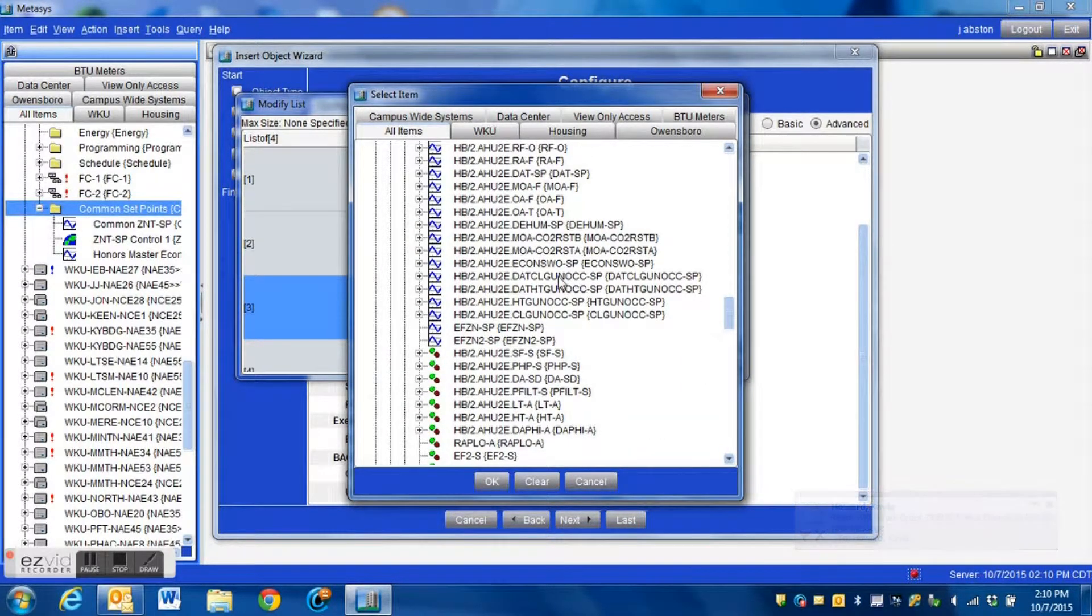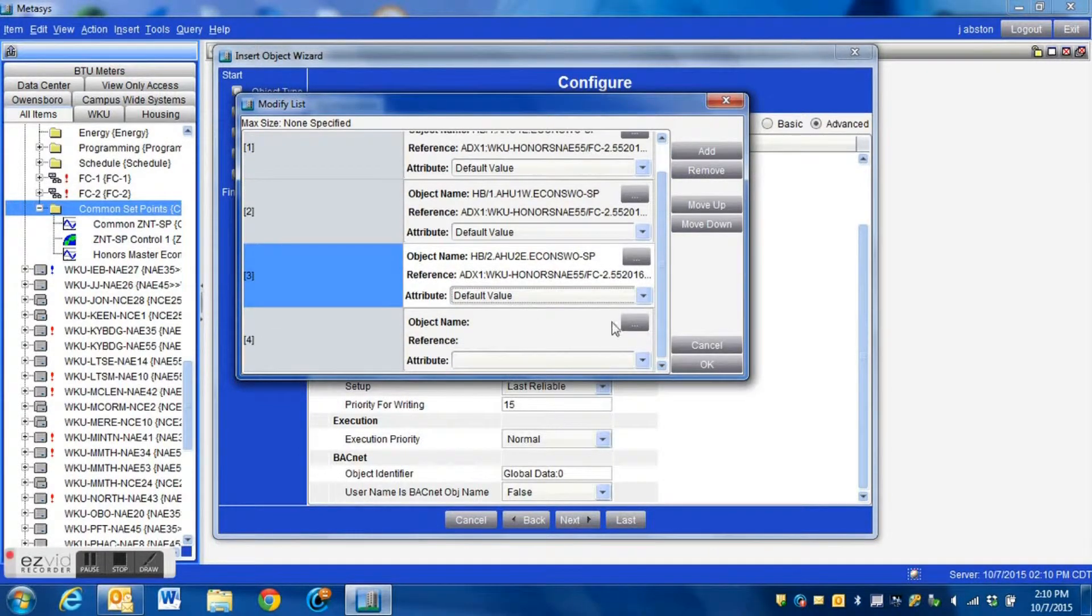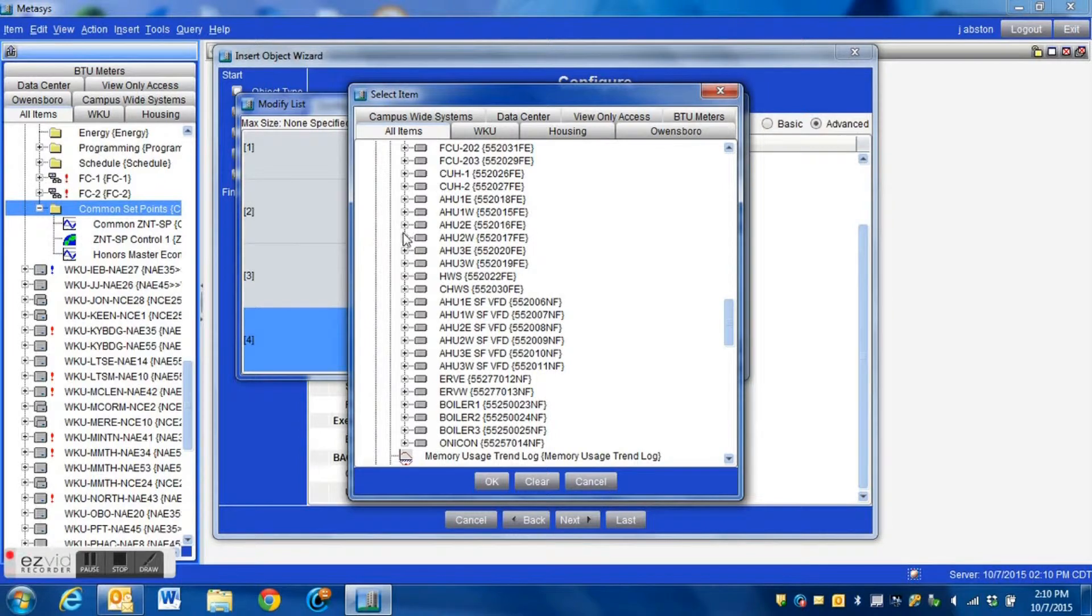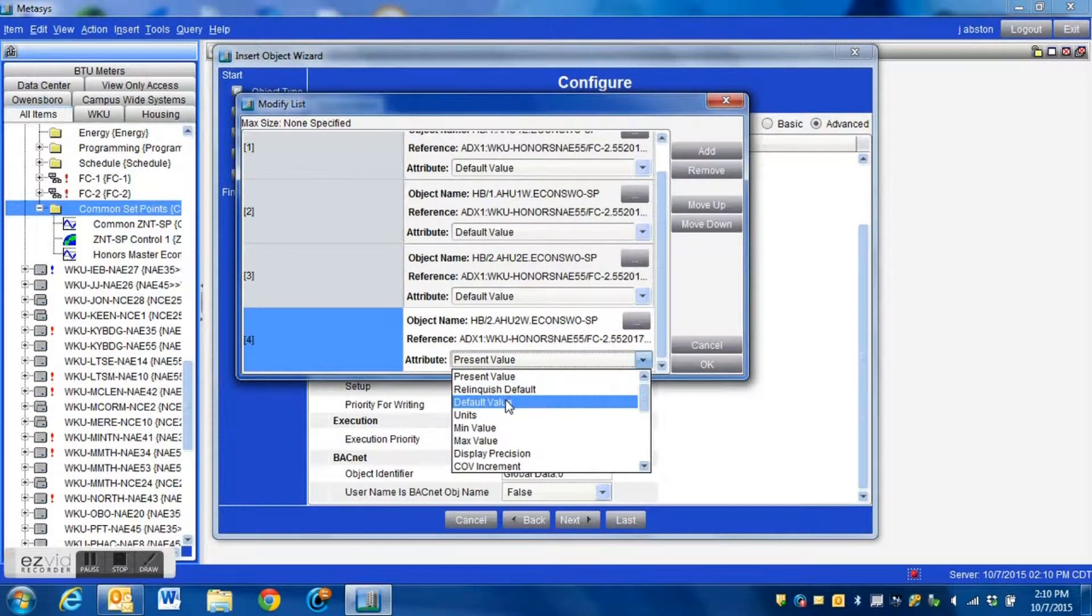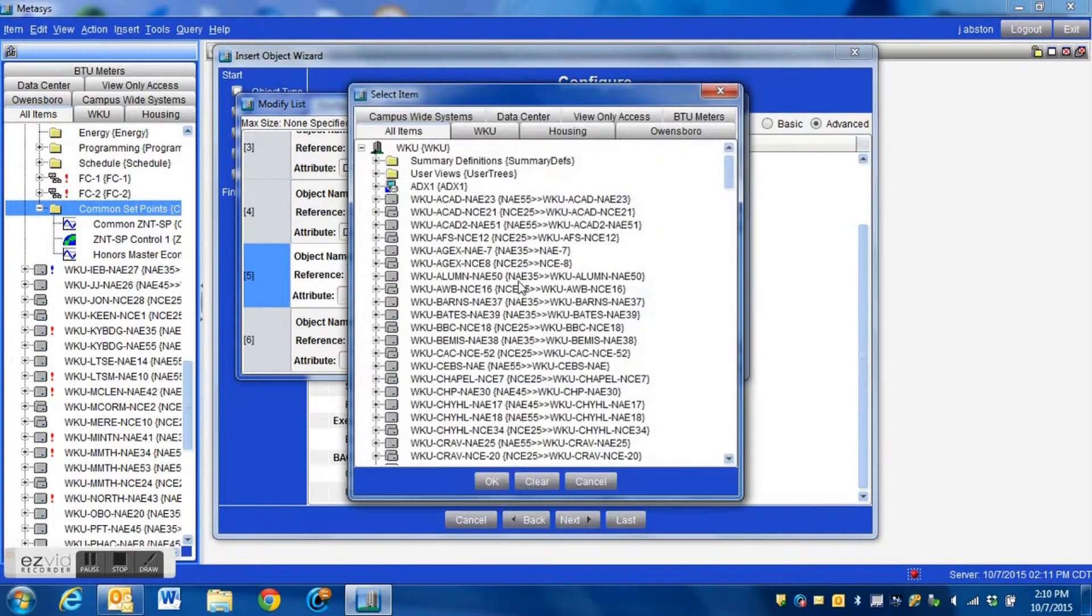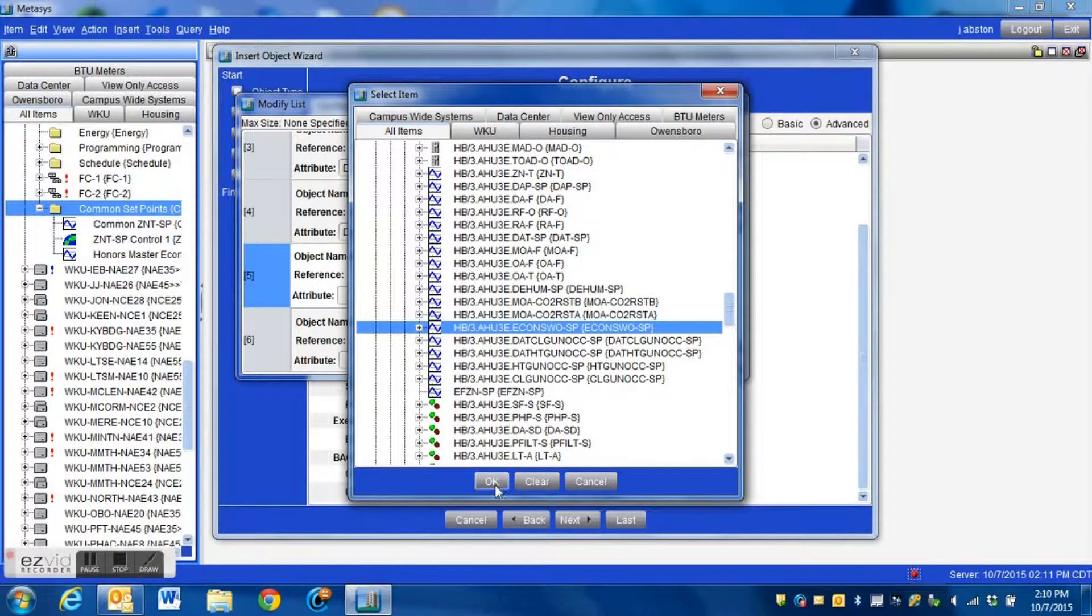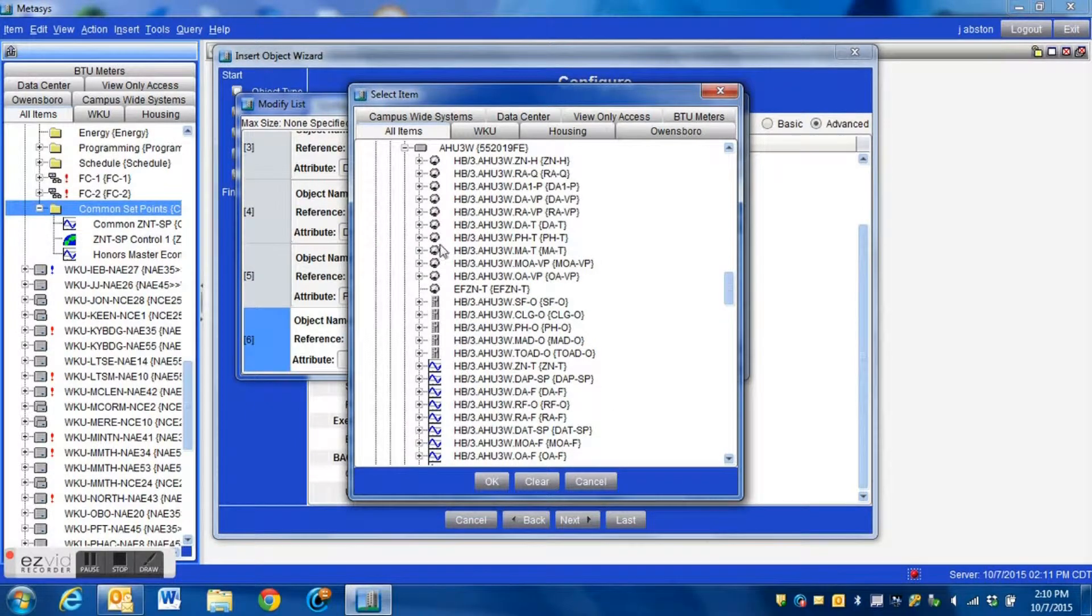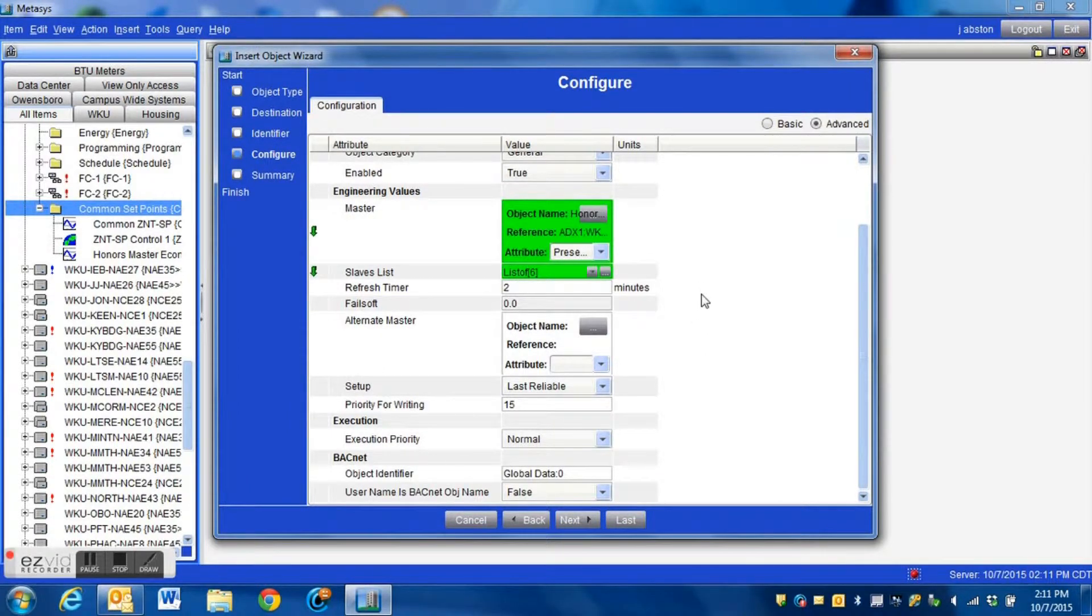This logic block is something that really makes it much easier to use instead of having to go to each air handler to adjust this set point. Using a global data like this is a great way to share one set point to all of the air handlers. These types of logic blocks work very well. This type of logic block is a great way of adjusting the entire common set point for a building as well or even simply breaking it up by the floors depending on how you use the space. You can simply put a master control point similar to what we did here with the economizer lockout and you can have that same data shared to each of those points.